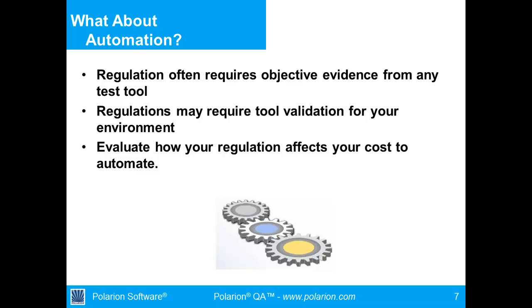So you made a really interesting point about big tools being hard to qualify in environments, Karen. And one way you deal with that is that if you're buying a big tool, you're not required to actually qualify all aspects of that particular tool. From an IQ, OQ, PQ point of view, you've got to install it, but you can focus the qualification on just those aspects of the tool that you're going to be using inside your R&D effort or in your production environment. And that can often, especially with the very big tools, make it simpler to qualify those particular products and get them to be used in production faster.